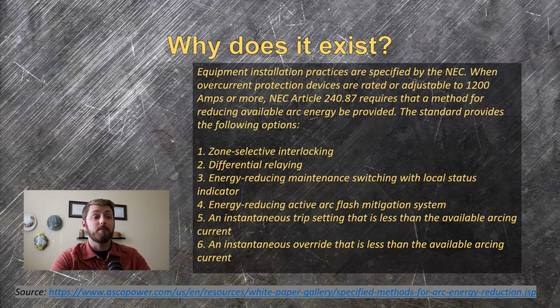Maintenance mode is one of very few systems whose sole purpose is decreasing the danger to people working on or near the switchgear. If you've been through NFPA 70E training, you'll know that the upper limit of what PPE can reasonably protect you from in an arc flash is about 40 calories per square centimeter. By enabling the maintenance mode switch, the incident energy of a system can be lowered dramatically, in some cases from well over 40 cal to something more survivable like 10.